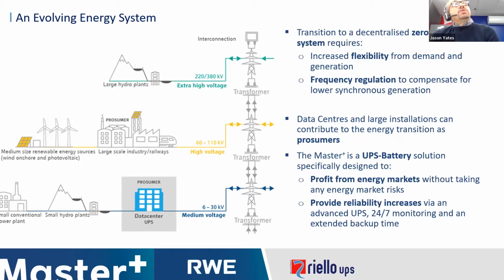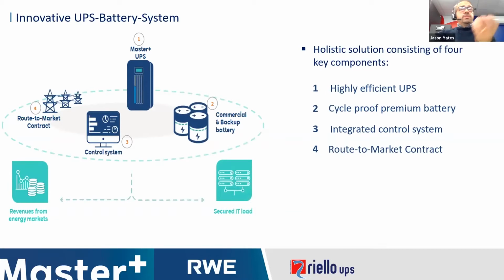Now, the Master Plus system that we developed is a specific UPS battery solution, which was designed to profit from the energy markets without taking any of the energy market risks, whilst at the same time providing reliability increases via an advanced UPS, 24/7 monitoring, and an extended backup time. The system that we developed comprised four key parts. The first part was a highly efficient UPS system. Second was the cycle-proof premium batteries. Then we had the integrated control system, and we obviously needed a route to market contract.